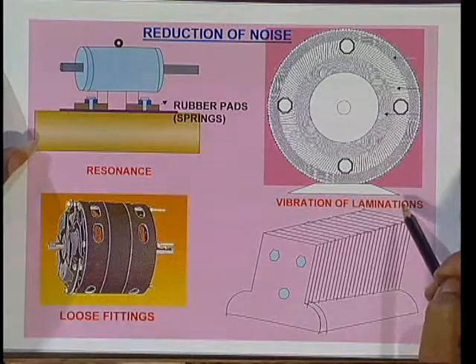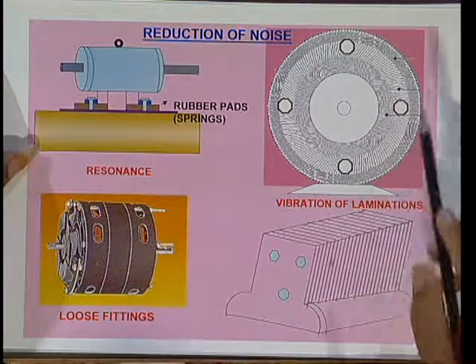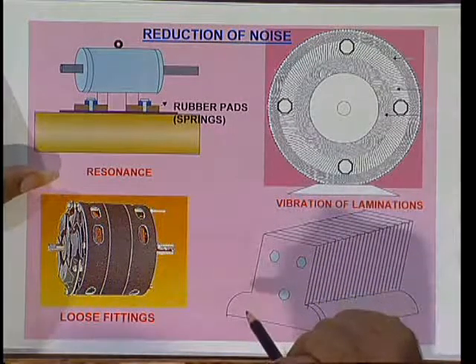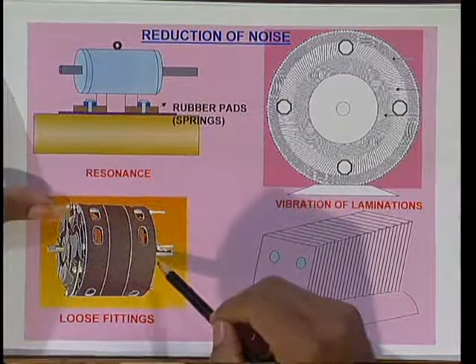To reduce eddy current losses in the motor, the core is laminated. If any air gap is present between the laminations, it creates magnetic noise. This can be reduced by tightening the rivets between the laminations. You can observe stator laminations or pole laminations in the case of DC motors. Another source is noise due to the loose fitting of nuts and bolts, which can be reduced by tightening the nuts and bolts of the motor.